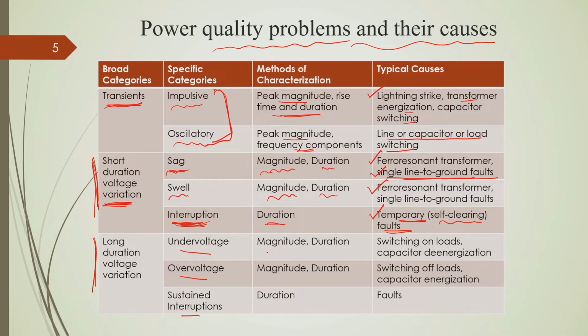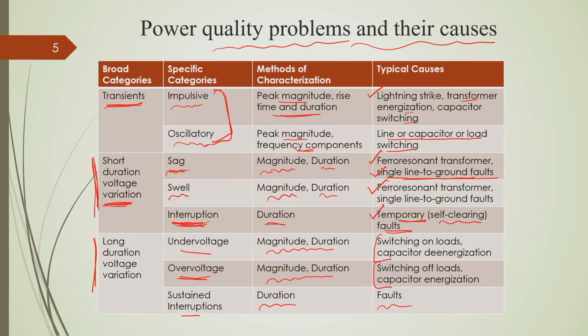This is also characterized by magnitude and duration, and the reasons are switching on a load, capacitor de-energization, etcetera. Similarly, over voltage is a sudden rise in voltage, and if it sustains for more than 1 minute, it is categorized as over voltage. It is also characterized by the magnitude and duration of the over voltage, and it occurs due to switching off a very large load. Similarly, when supply voltage becomes 0 for more than 1 minute, it is categorized as sustained interruption, and it occurs due to faults, as we know.